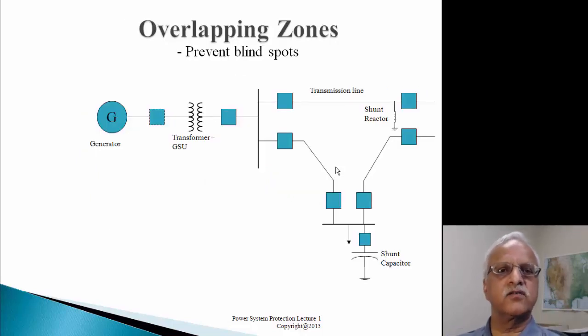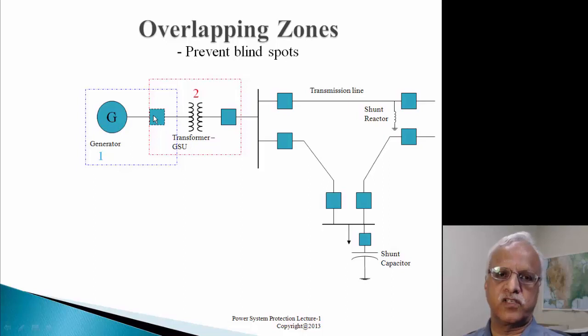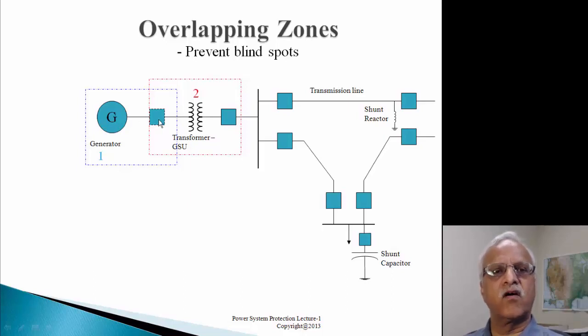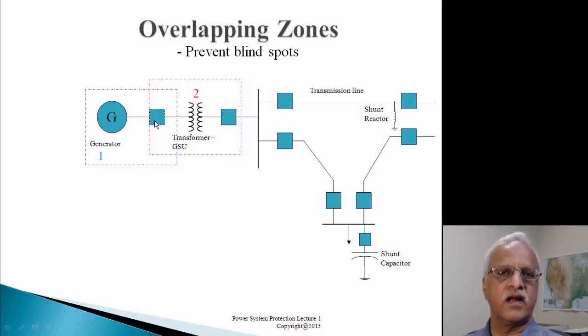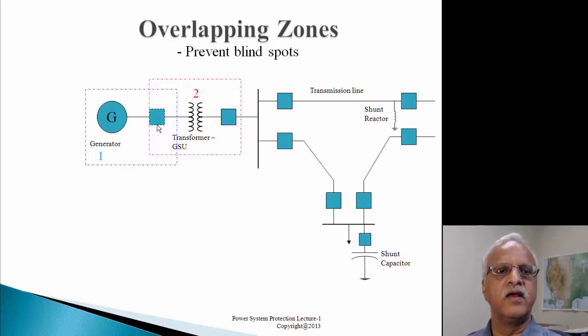A second key aspect of zones of protection is that you need overlapping zones. You don't want a transformer zone that covers only the transformer without including the devices outside it. Similarly, for a generator, you don't want a CT only on one side, because if a fault occurs inside the breaker, you may not be able to identify it as part of the generator protection. So the generator protection and transformer protection are overlapping. If a fault is common to both zones, both protection schemes operate and take corrective actions.